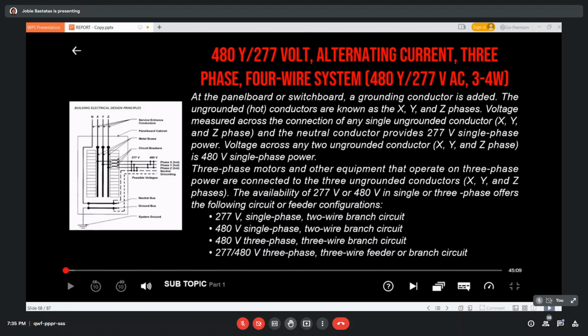The availability of 277 volts or 480 volts in single or three phases offers the following circuit or feeder configurations: 277 volt single-phase two-wire branch circuit, 480 volt single-phase two-wire branch circuit, 480 volt three-phase three-wire branch circuit, and 277/480 volt three-phase four-wire feeder or branch circuit.